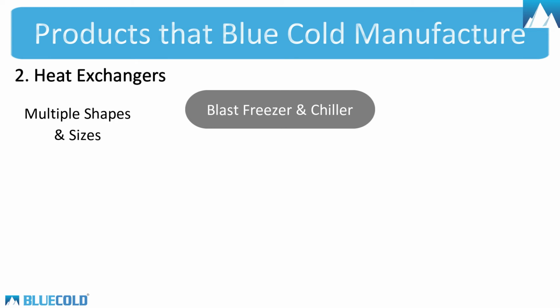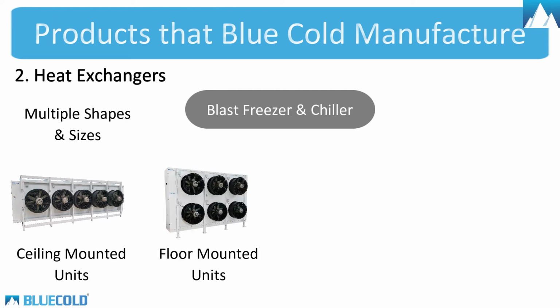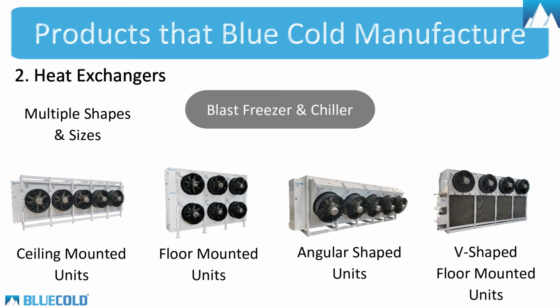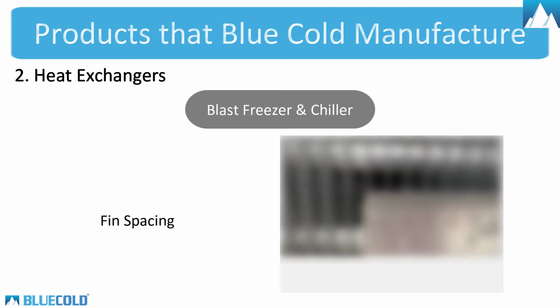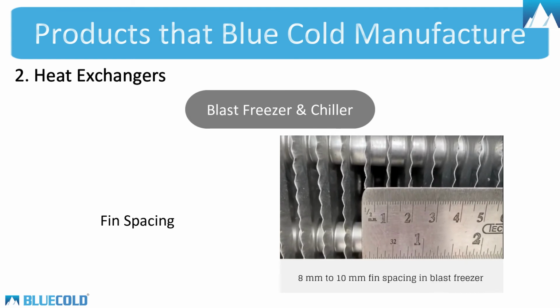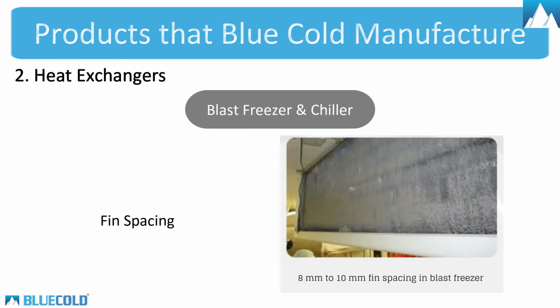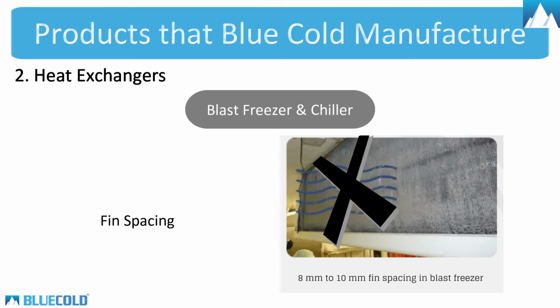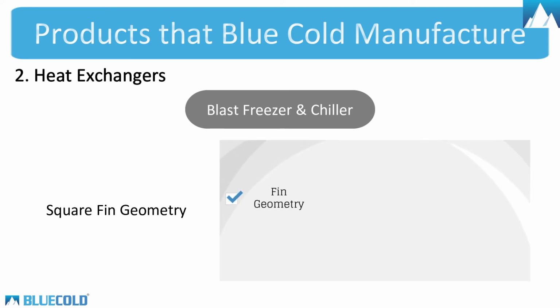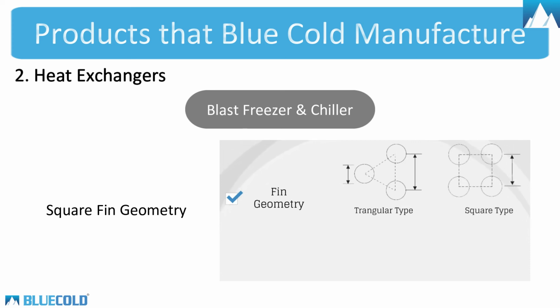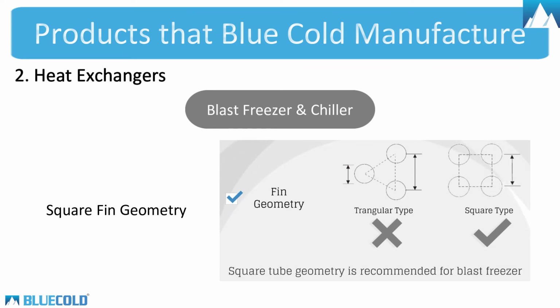Multiple shape and size options. Depending on the size and shape of the room, you should decide which type is more suitable for you from the below options: ceiling mounted units, floor mounted units, angular shaped ceiling mounted units, V-type floor mounted units. Fin spacing. Our blast units have a minimum of 8 to 10 mm fin spacing to ensure that the frost formation between the fins during the blast freezing process does not choke or block the airflow. Square fin geometry. There are two main types of fin geometry: the triangle type and square type fin geometry. The square fin geometry is most suitable for the blast freezer and enables high airflow and less air pressure drop. So always ensure that the square type fin geometry is used in your blast freezer.